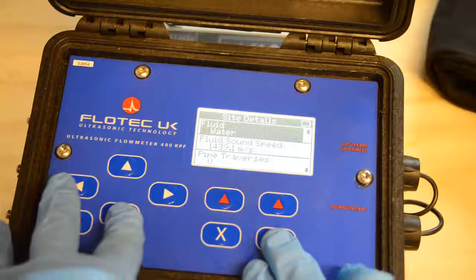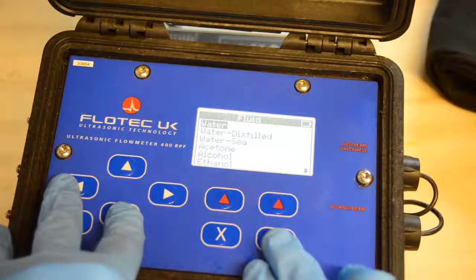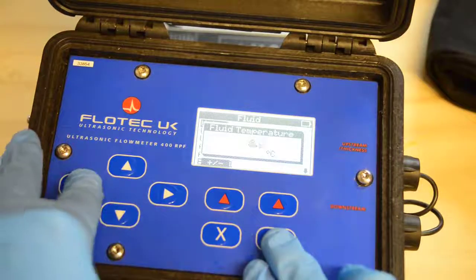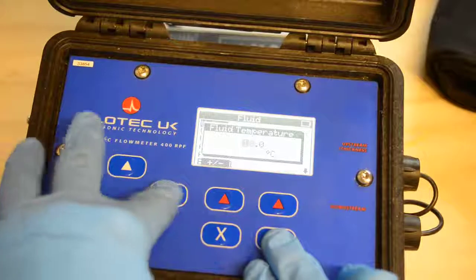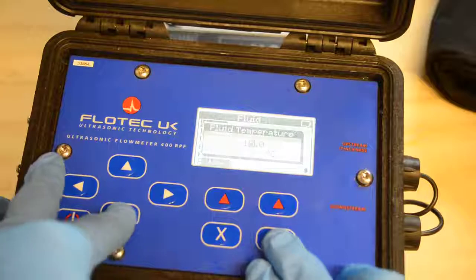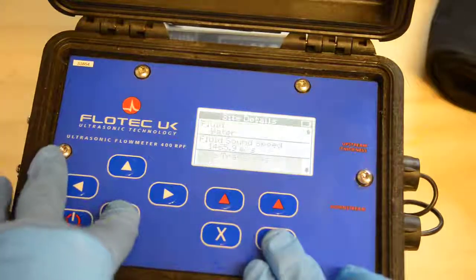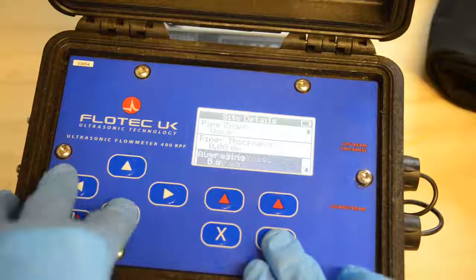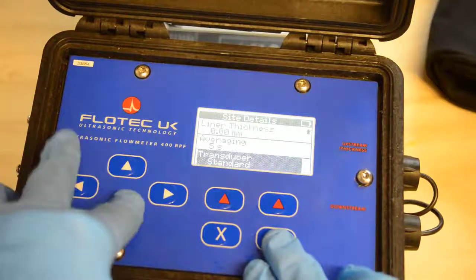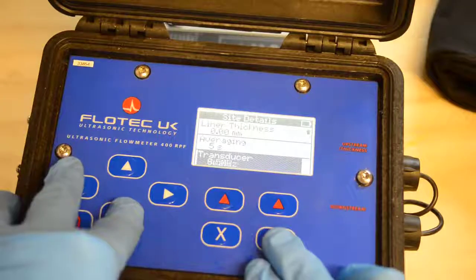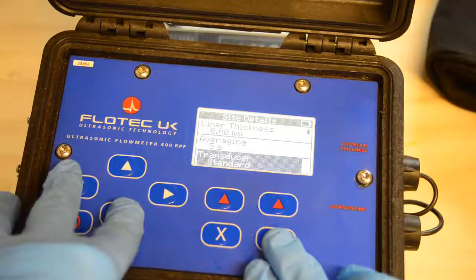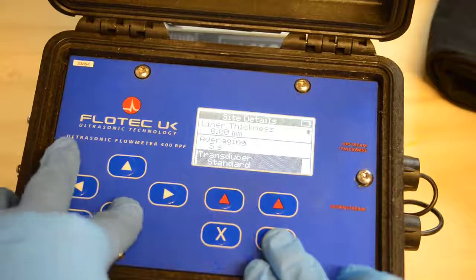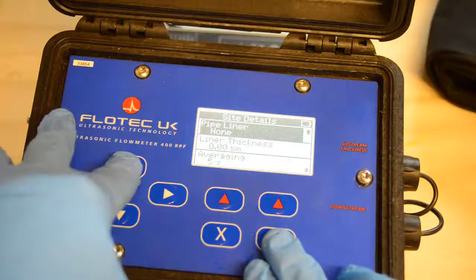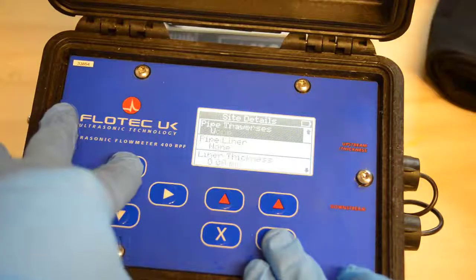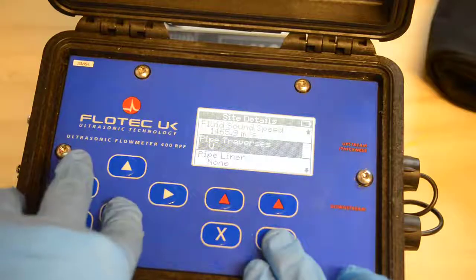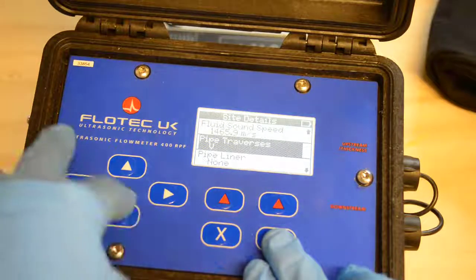Now, when you have water, if you know the temperature, you can enter it here. Now, the flow meter does correct for temperature, but it's good to get the setup just right if you can. And then you get the averaging, and then you get a choice of sensor. Today we've just got the standard sensor. So let's just check that. We've got no liner on this pipe, and we're going to go in V mode. That's where we have two sensors on the same side of the pipe.